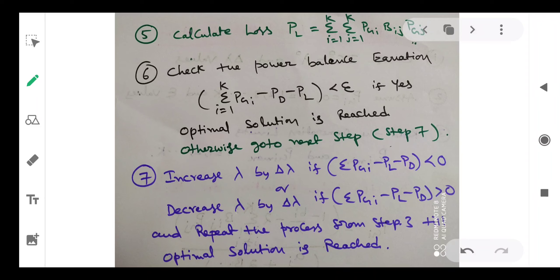Fifth step: calculate the power loss PL = ΣΣ PGi·Bij·PGj, where i and j go from 1 to K. This is the product of generation and B coefficients. Once you calculate the PL value, you have the PG value and PL value. With constant demand PD, check the power balance equation: |ΣPG − PD − PL| less than epsilon. This is the power balance equation.